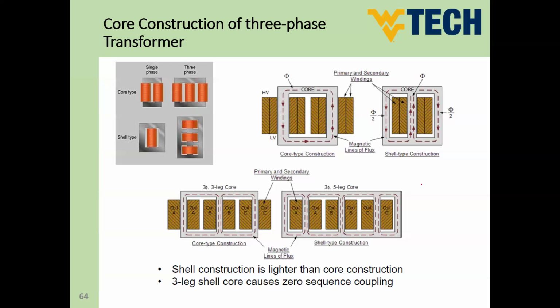What is the meaning of zero sequence? You know, guys, regarding the harmonics, the zero sequence is nothing but the summation of the three phases. So if I would like to write the zero sequence in terms of the third harmonic, for instance, I third harmonic is going to be (IA + IB + IC) divided by 3. So this is called the third order.